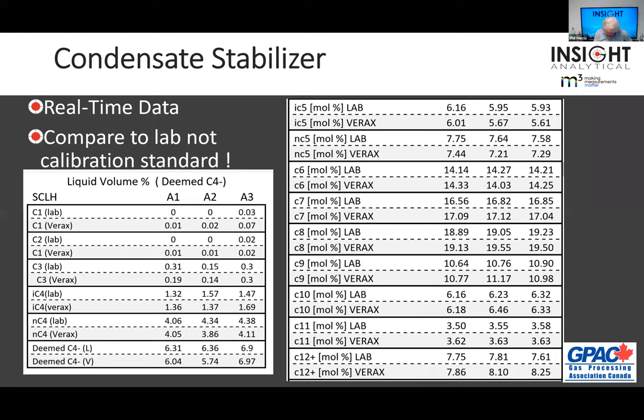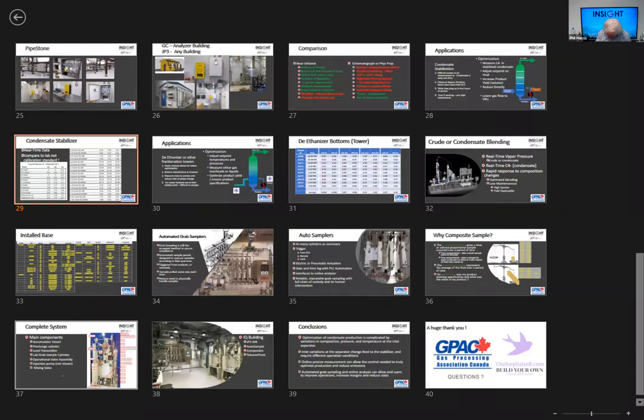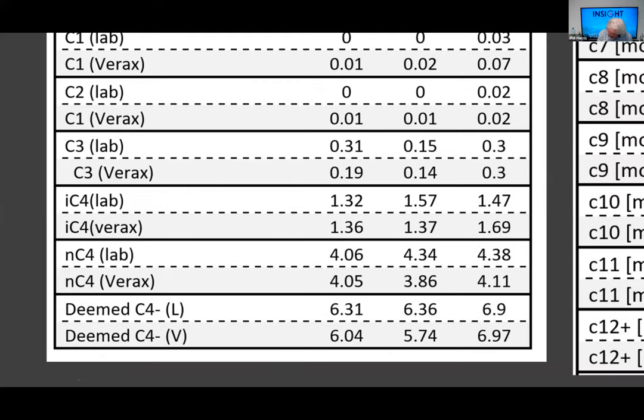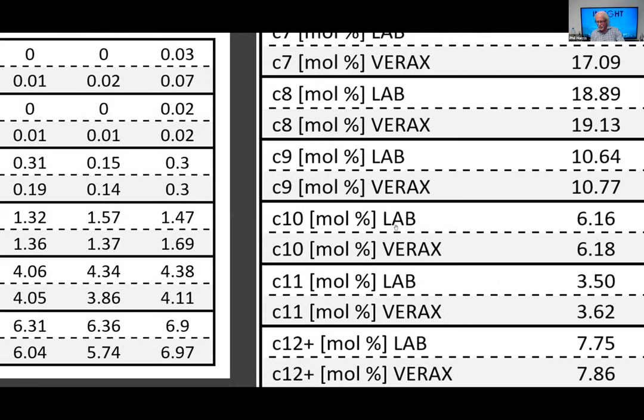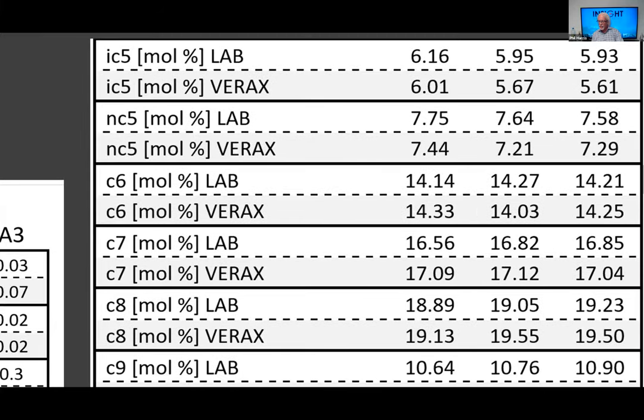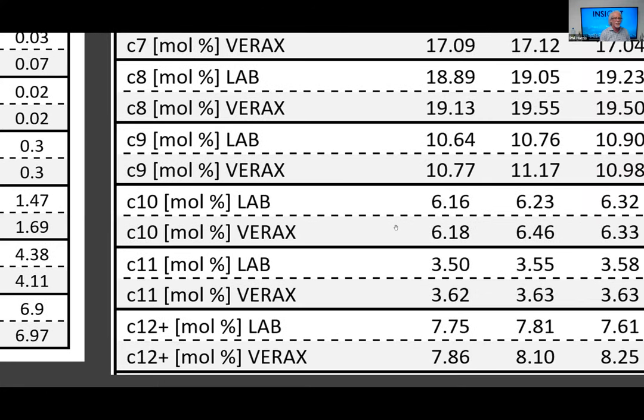Here's how this runs in practice — comparing lab results to online analyzer results. These are samples pulled out and taken to a remote lab, compared to the online analyzer results. We get pretty close on iC4, pretty close on C3, pretty close on nC4. The deemed C4 minus values are really close. Those are three different condensate stabilizers — three different measurement points, all running under the same analyzer with 30-second updates on C4 minus. And we're not just doing the C4 minus — we're actually doing a complete C5, C6, C7, C8, C9, C10, C11, and C12 analysis all at the same time. Full chemical composition of the condensate done nearly in real time.